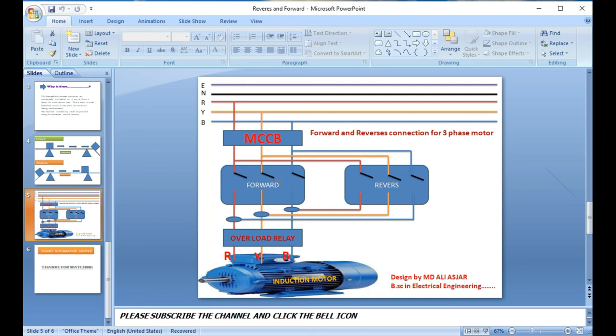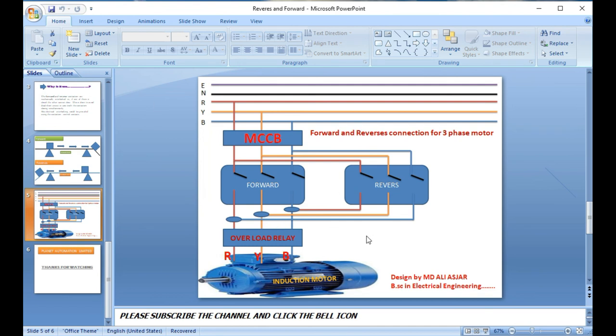For forward, the phases are connected directly to the motor. For reverse, one phase is swapped — for example, R is connected to the Blue terminal. You can change any one phase, but when you do, two phases must change together and one phase remains fixed. That is the main condition of the reverse system. These connections cause the motor to rotate in the opposite direction — counterclockwise or anti-clockwise. This is the basic wiring connection for forward and reverse.